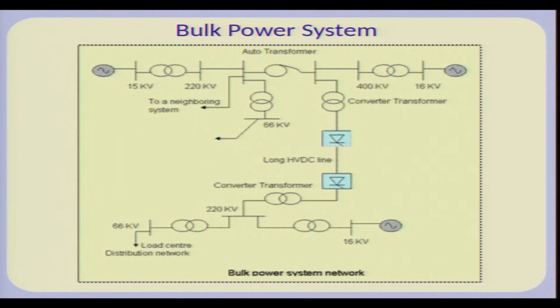Now, one of the important aspects of a bulk power system, as compared to a lower voltage grid, is that usually at the bulk level, transmission lines are meshed. That ensures a great deal of reliability. Another thing is that although loads themselves could have a little bit of unbalance, they could be single phase loads, once you aggregate loads in the distribution system, by the time you reach the transmission system, when you look downstream, more or less the loads are balanced because of a large amount of averaging which takes place. So, the bulk power system, the high voltage grid, is mostly a 3-phase balanced system, and it is a meshed system, that is, there are parallel paths in AC transmission or DC transmission, and also more or less a balanced system.